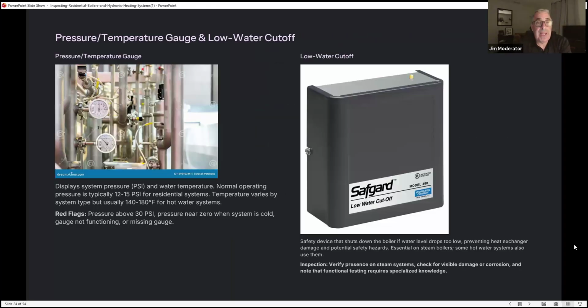Pressure, temperature gauge, and low water cutoff. The pressure and temperature gauge displays the system's pressure, the PSI, and the water temperature. Normal operating pressure is typically between 12 and 15 PSI for residential systems. Temperature varies by system, but is usually 140 to 180 degrees for hot water systems. Red flags: pressure above 30 PSI, pressure near zero when the system is cold, a gauge not functioning, or a missing gauge.